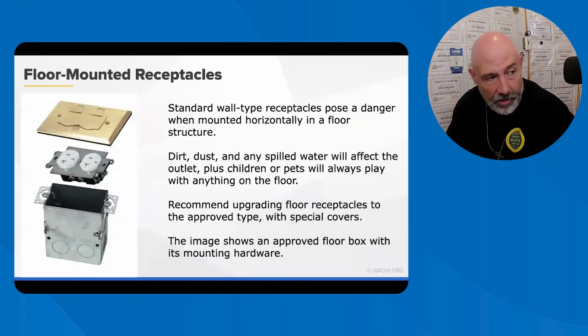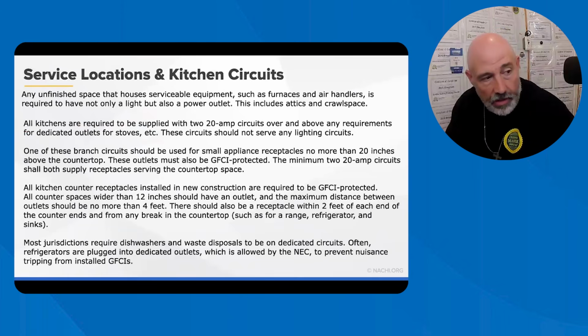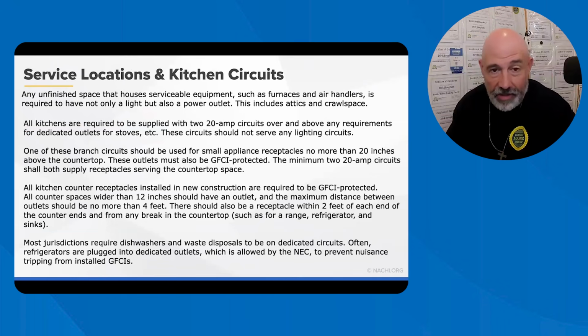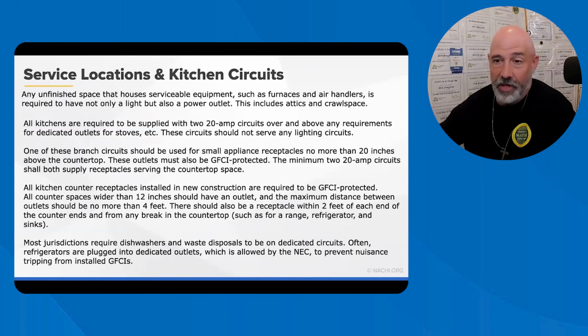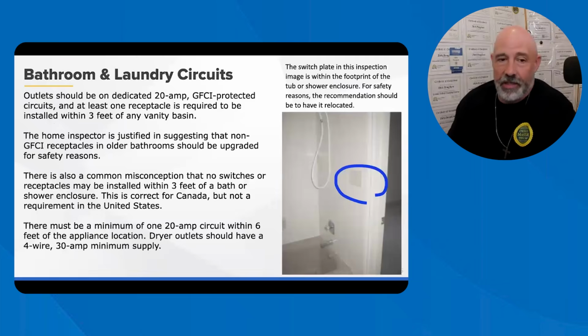Same thing here with receptacles. Make sure that they're mounted properly to the floor and make sure that they are sealed with that proper weatherproofing outlet top so that you don't spill into it. In service, you're looking at locations in the kitchen and any wet area. You want to make sure that there's GFCIs. Kitchen countertops should have at least 12 inches required within any point of the countertop, not more than 24 inches from any outlet, so that you can plug in multiple things around there and not be stringing any electrical cords. That's the bottom line: you don't want to have electrical cords, and a lot of them aren't sized properly anyways when you're using those extension cords. So the goal of the rule of thumb is to make electricity convenient enough for people so they don't have to use that. So that's it.